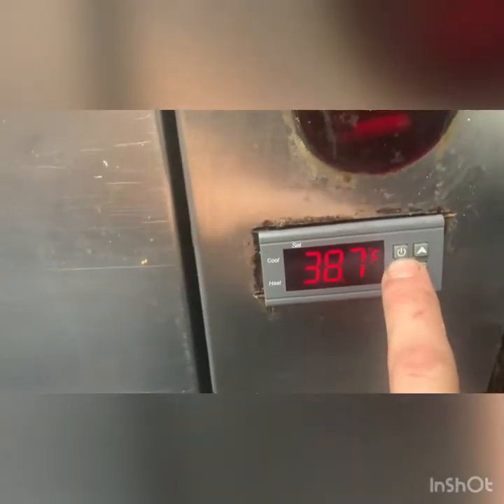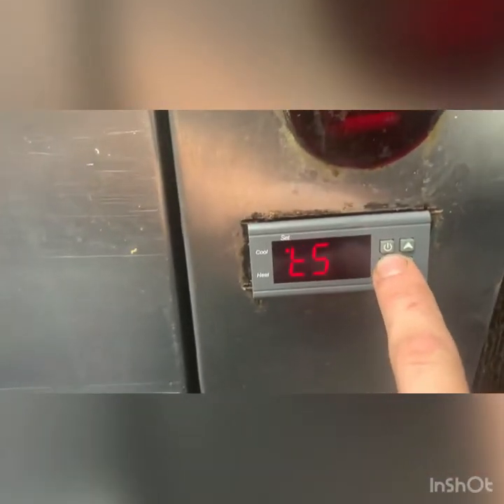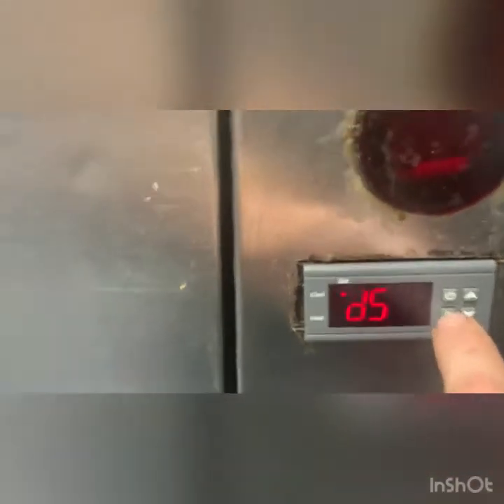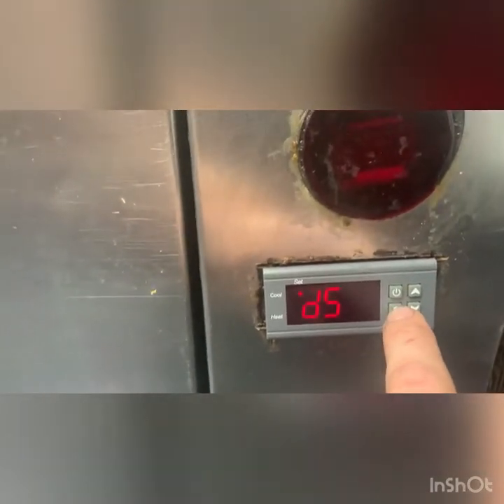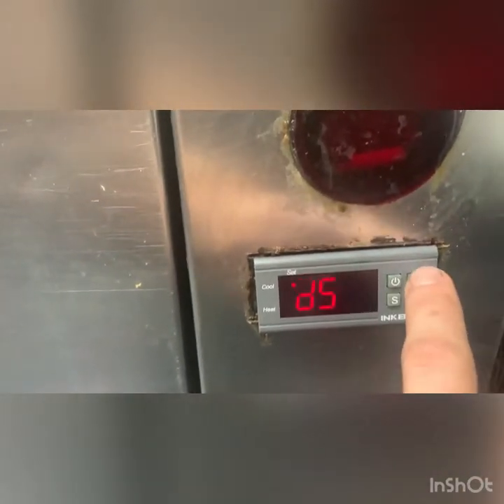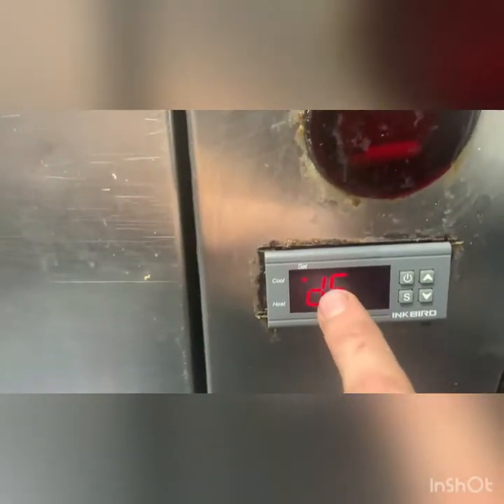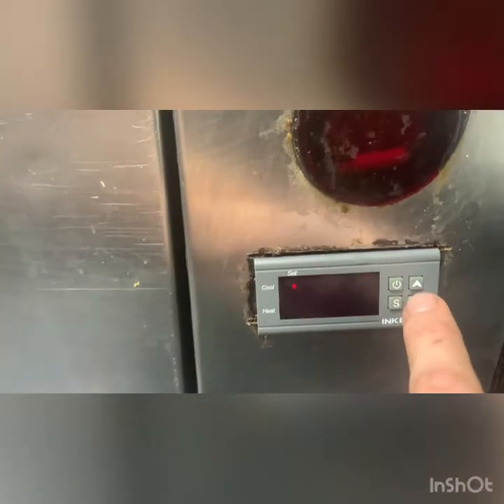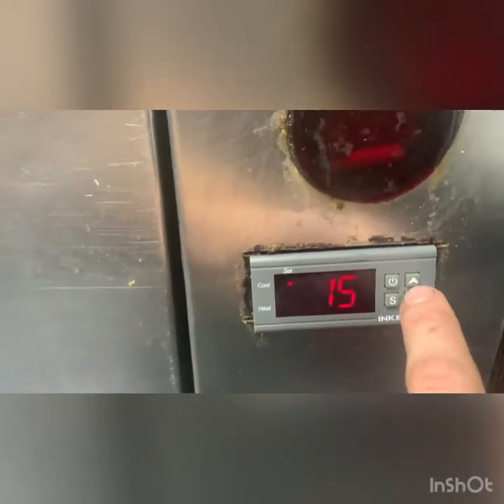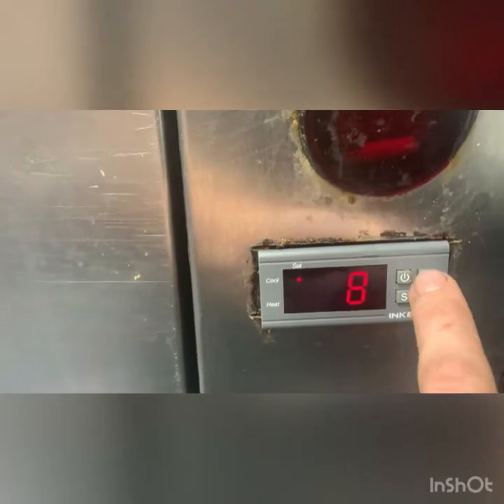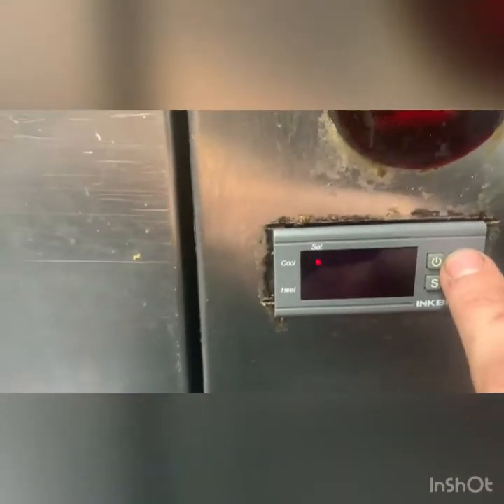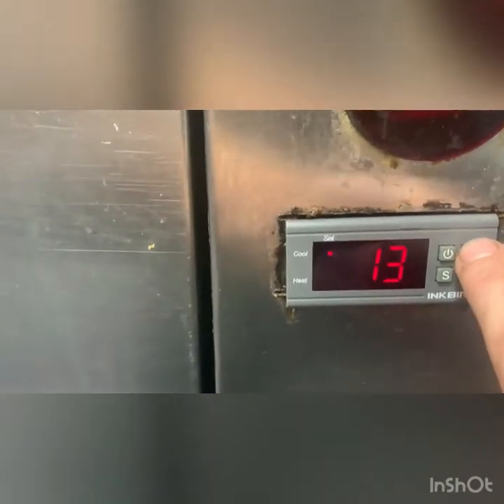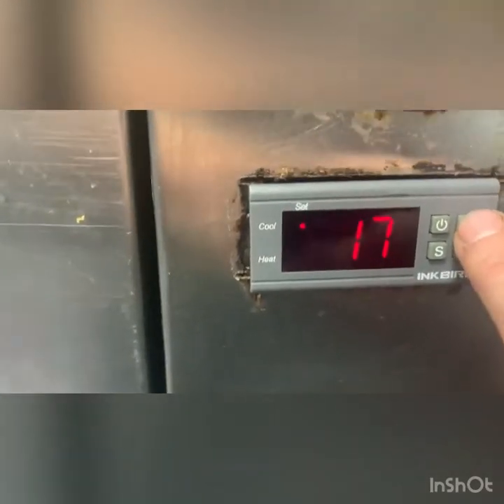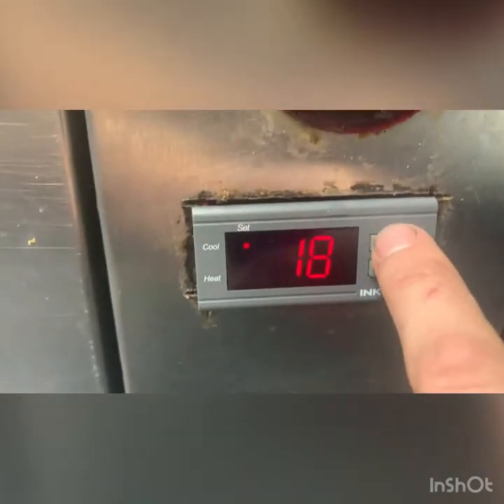Now, at 20, it's going to freeze, right? When the coil freezes, it doesn't pass air, and then it freezes up and starts a nasty cycle. So it's going to shut off at 20. Now, the DS is the differential. That's where it's going to kick on. So at 20, let's keep it simple, plus 10, now we were coming on at 30. Nope. 32, 33, 34, 35, 36, 37, 38. So at 38, it's going to kick on, and it did.